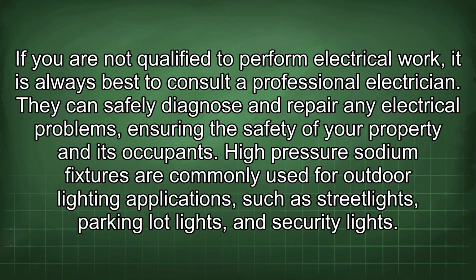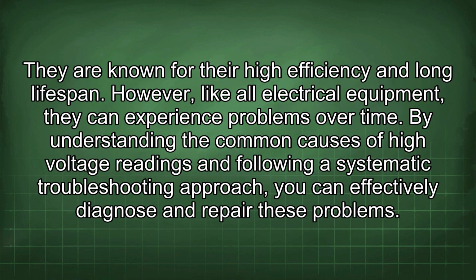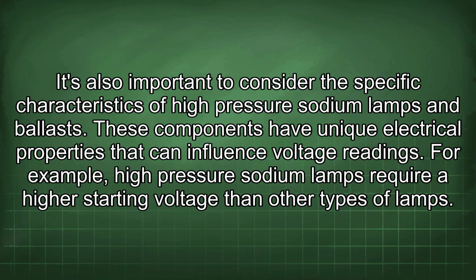High-pressure sodium fixtures are commonly used for outdoor lighting applications such as streetlights, parking lot lights, and security lights. They are known for their high efficiency and long lifespan. However, like all electrical equipment, they can experience problems over time. By understanding the common causes of high voltage readings and following a systematic troubleshooting approach, you can effectively diagnose and repair these problems. It's also important to consider the specific characteristics of high-pressure sodium lamps and ballasts.